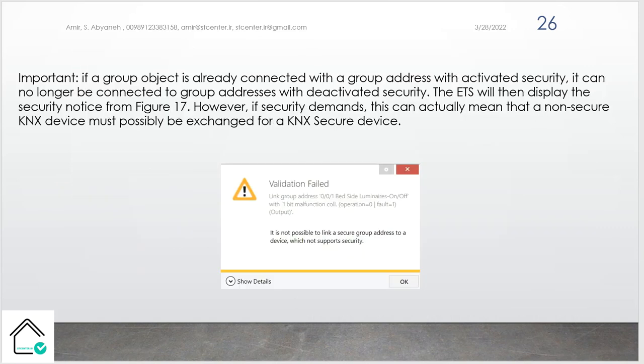Important: if the group object is already connected with the group address with the activated security, it can no longer be connected to a group address with the deactivated security. The ETS will then display the security notice from the figure below. However, if security demands, this can actually mean that the non-secure KNX devices must possibly be exchanged for KNX Secure devices.